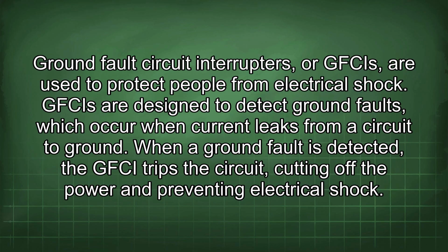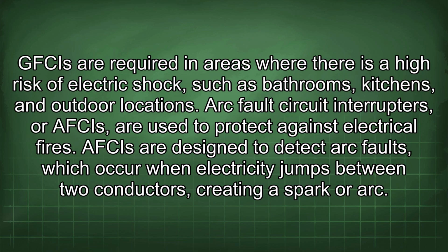Ground fault circuit interrupters, or GFCIs, are used to protect people from electrical shock. GFCIs are designed to detect ground faults, which occur when current leaks from a circuit to ground. When a ground fault is detected, the GFCI trips the circuit, cutting off the power and preventing electrical shock. GFCIs are required in areas where there is a high risk of electric shock, such as bathrooms, kitchens, and outdoor locations.